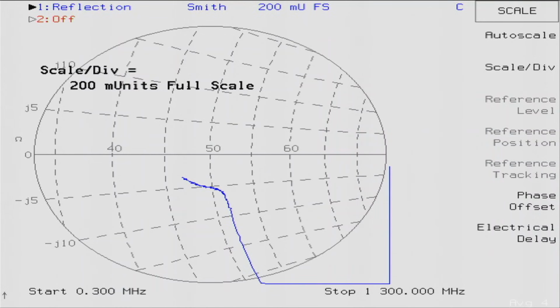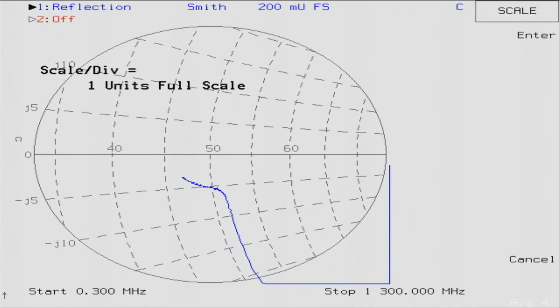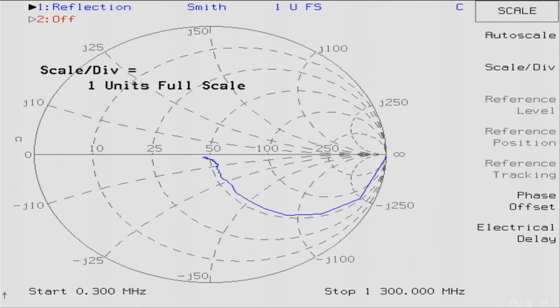Let's check the short calibration, make sure our calibration is correct. I like to double check things. There are some things that are very, very easy to check when you do calibration. You can make sure your load is looking good, your short is looking good. Yeah, there we go. See, we have a very nice calibration. Our short is exactly where we want it to be.